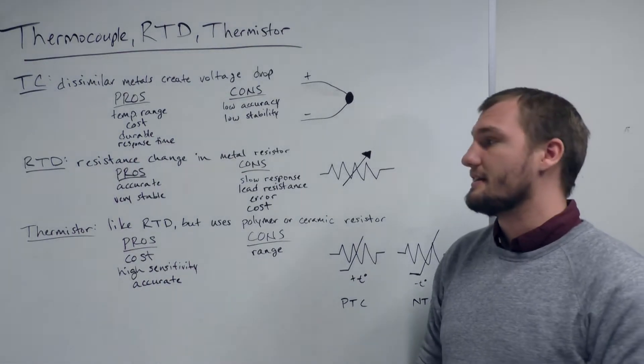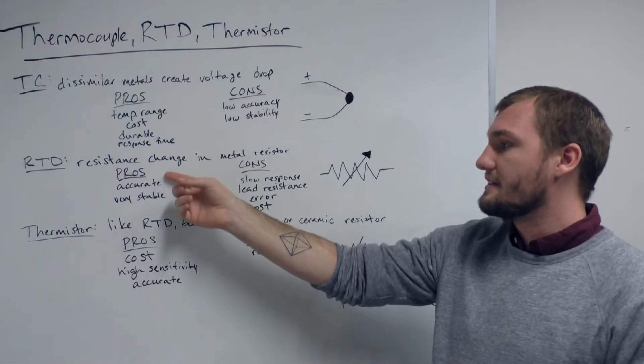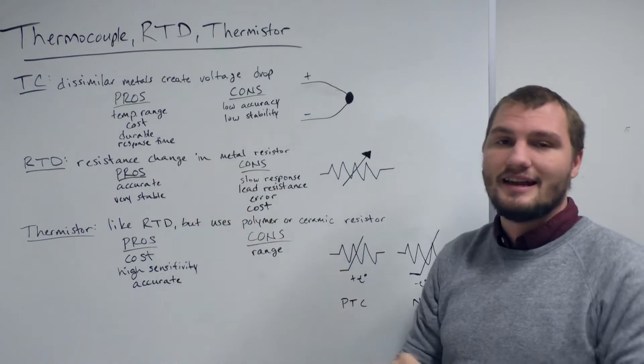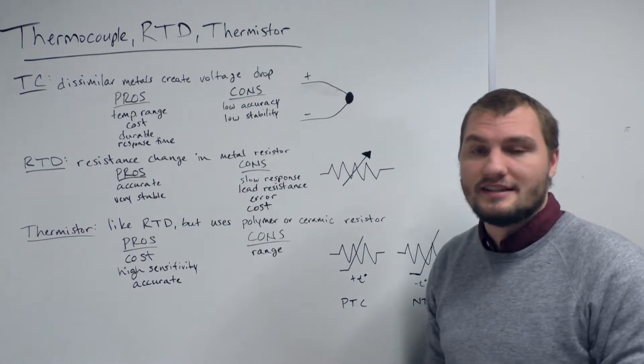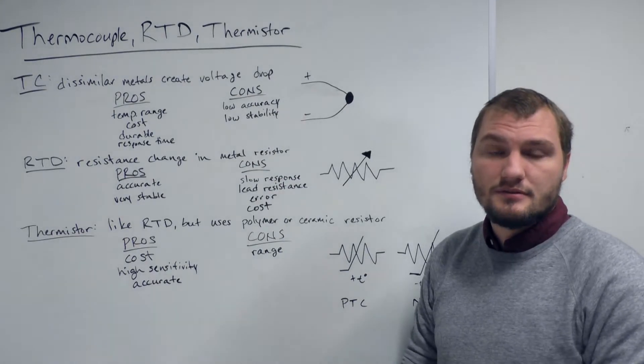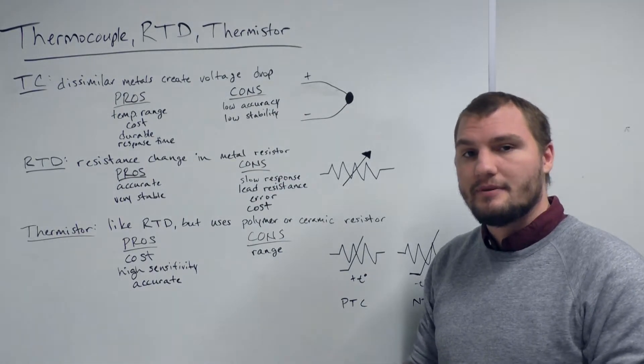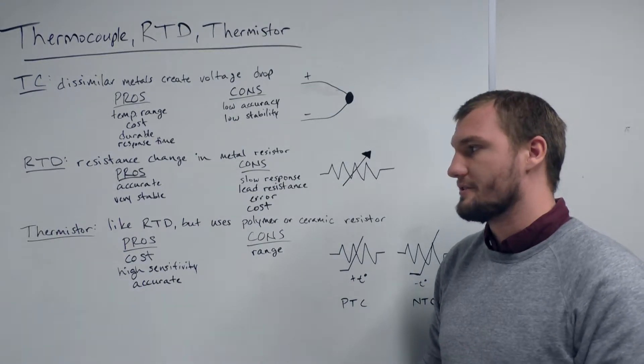An RTD, on the other hand, is a device that measures the resistance change in a calibrated metal resistor. A typical version of an RTD would be a PT100, which is a platinum wire calibrated to be at exactly 100 ohms at zero degrees Celsius.